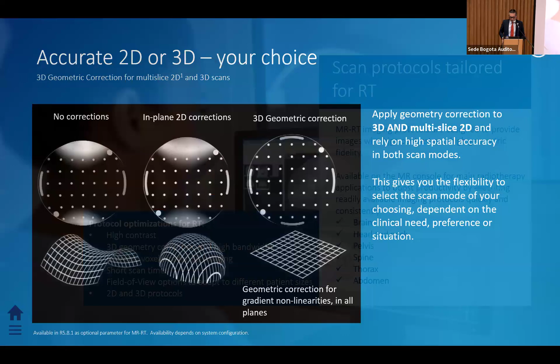The first one, the geometry problem. We can use different methods based on calibration and some specific phantoms, and we can use specific gradients with high-level specs to reduce this kind of deformation that is very common on MRI. So in these systems, we can use different geometry corrections. For instance, this is the 3D geometry correction that is available for a regular MRI system, used for radiology diagnostic, not for radiotherapy. This kind of correction is not the best, but it works for these purposes.